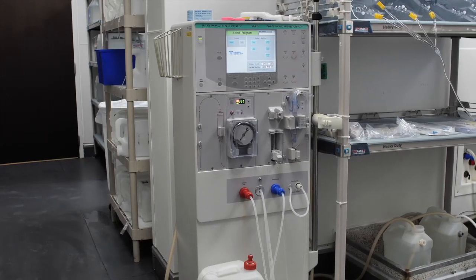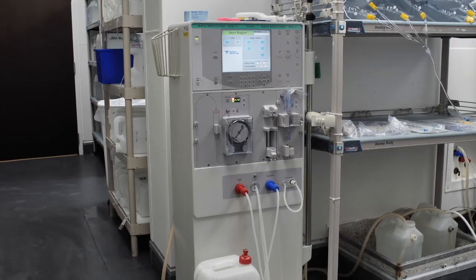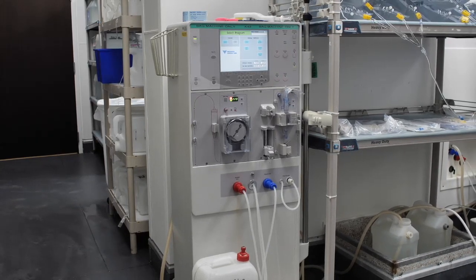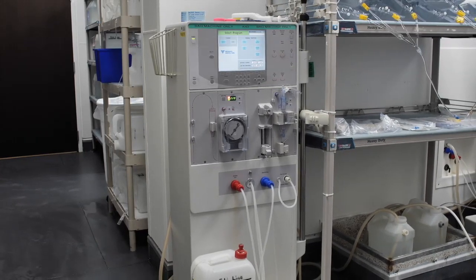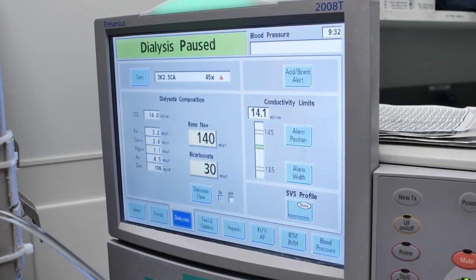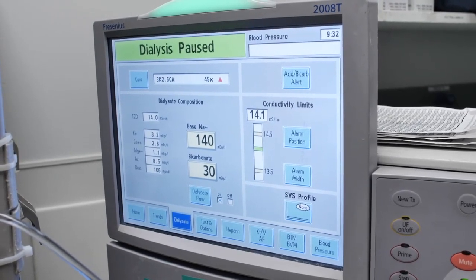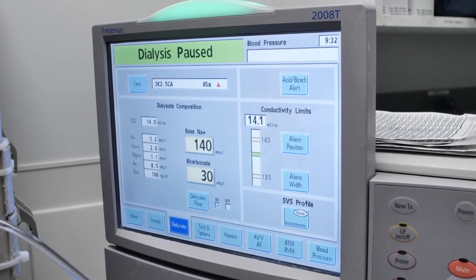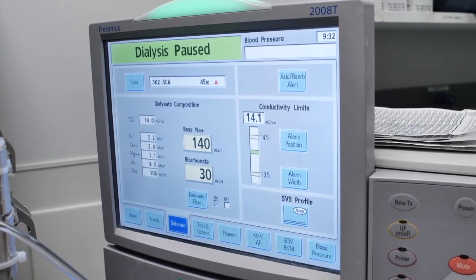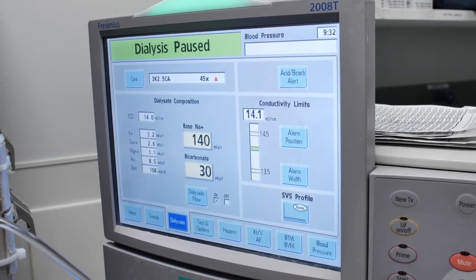This solution is a replication of the standard dialysate used during intermittent bicarbonate hemodialysis with the correct ionic composition and physiological temperature. Conductivity is set at a sodium concentration of 140 mEq per liter, potassium is 2-4 mEq per liter, bicarbonate is 30 mEq per liter.